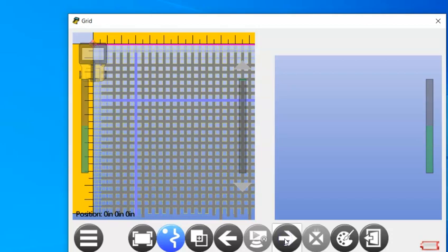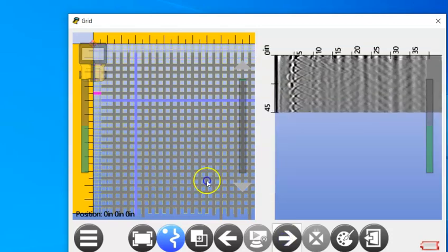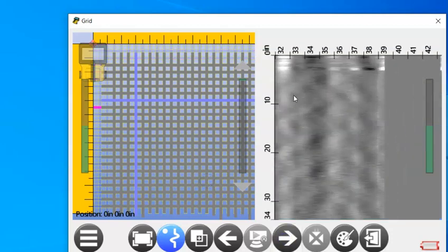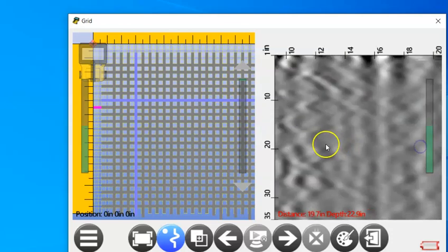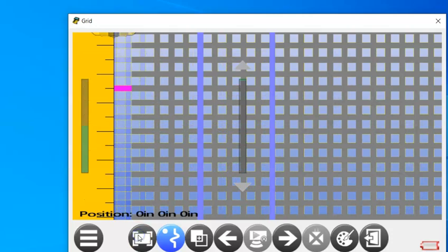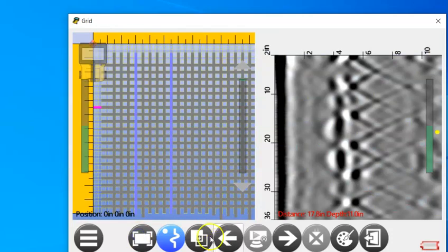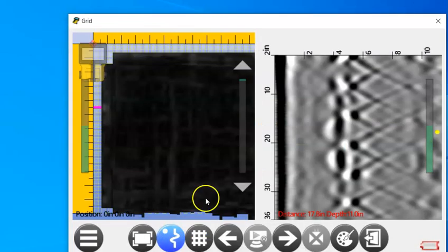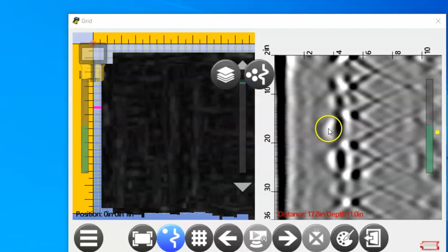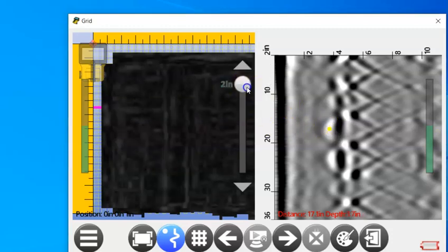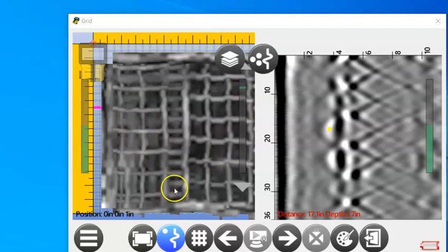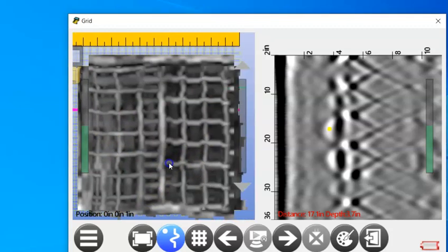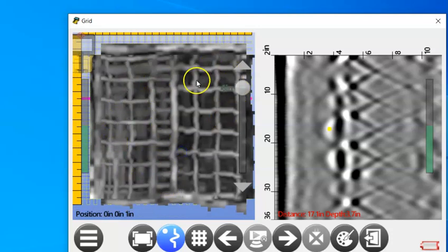Now some of the big things that we did change here in this new version of Veltha are going to be in your C scan, which is the 3D tomography here. So what you can do is make that full screen. Let's merge that data here. We're going to slice down to about, looks like these rebar are about 3.7, let's go down to four inches. There we go, and now we have a really good view here of that rebar mat, the two rebar mats.